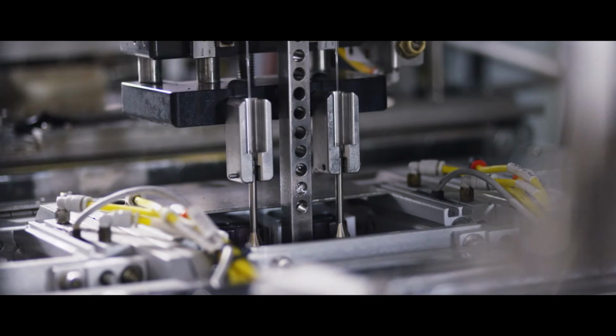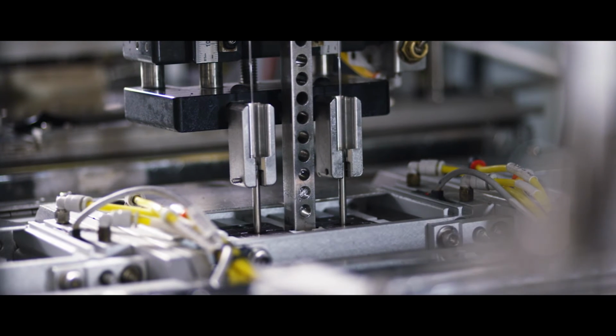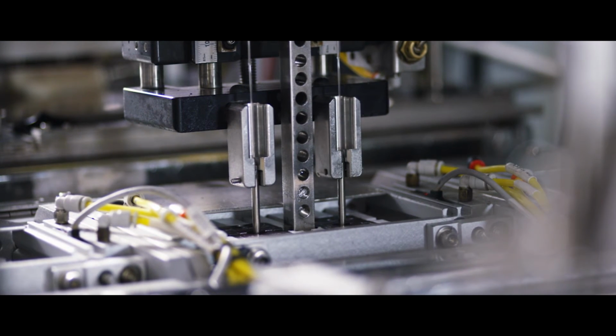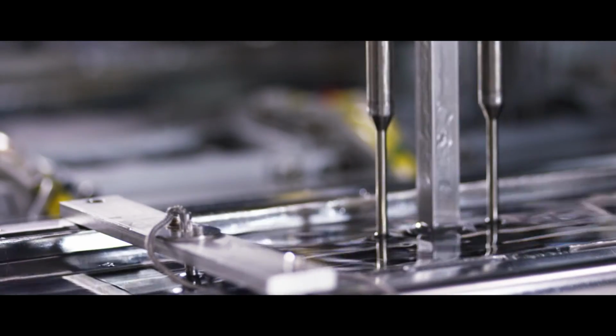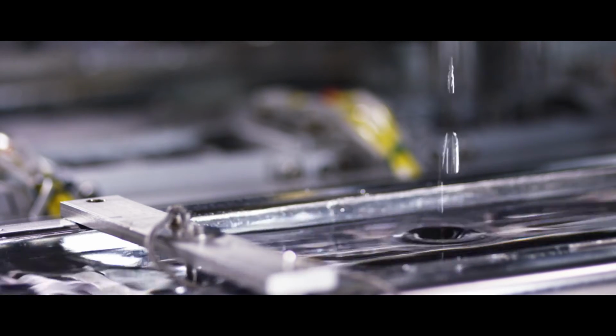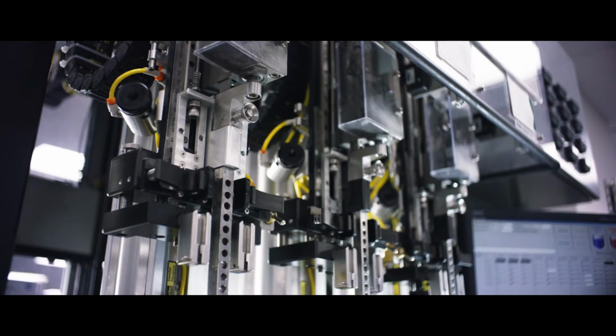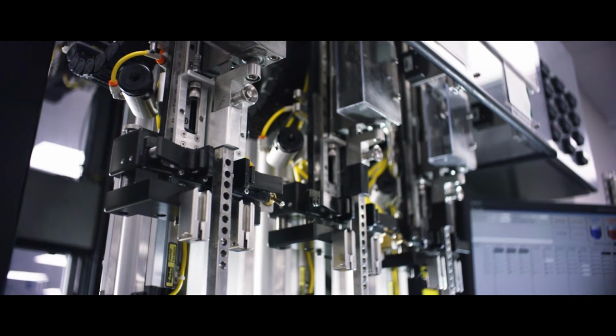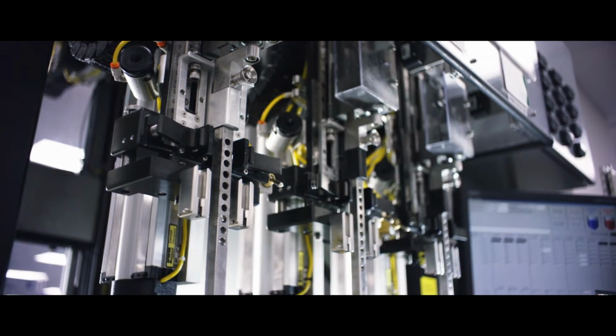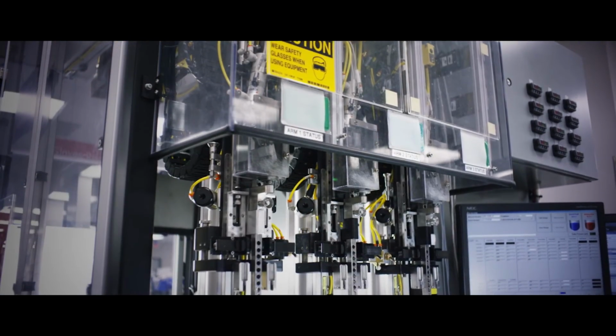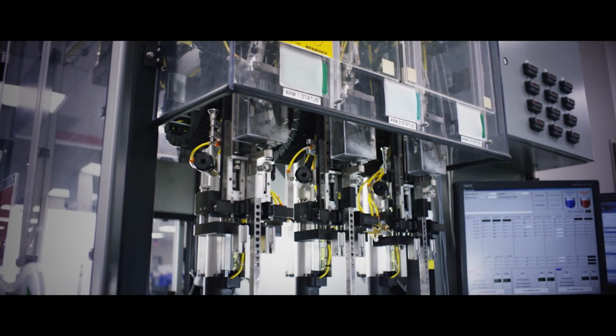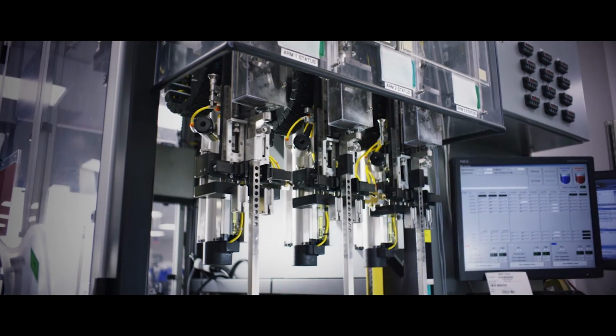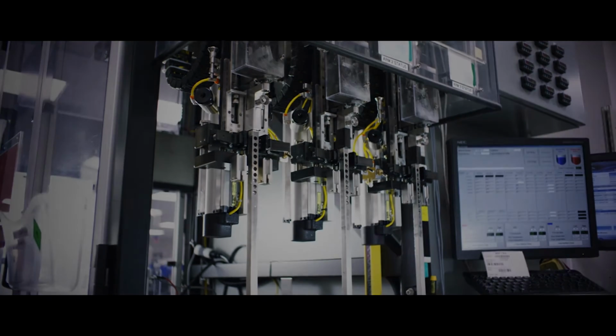Through extensive research and experimentation, we discovered that using thermal clamps between the hot and cold water baths produced improved crystallization. The next challenge was to find an efficient way to incorporate the solution into our own manufacturing process. The result is our six-axis molding, or SAM tower. $250,000, 1,000 balloons a day behemoth. It's a Boston Scientific exclusive.